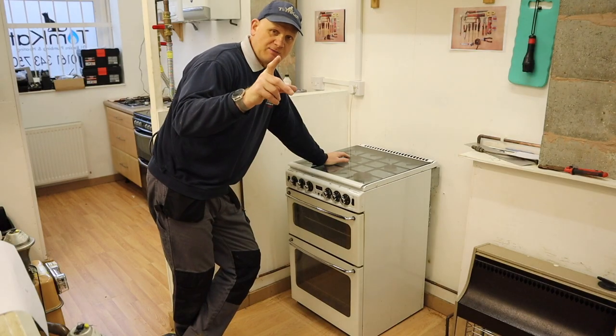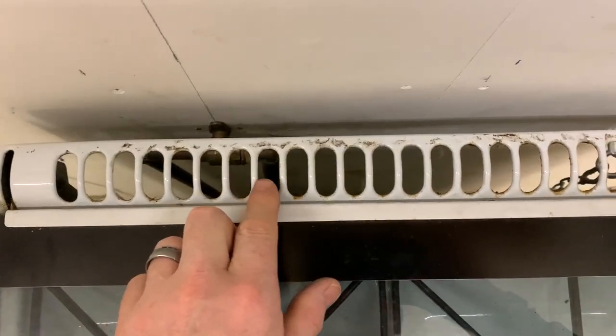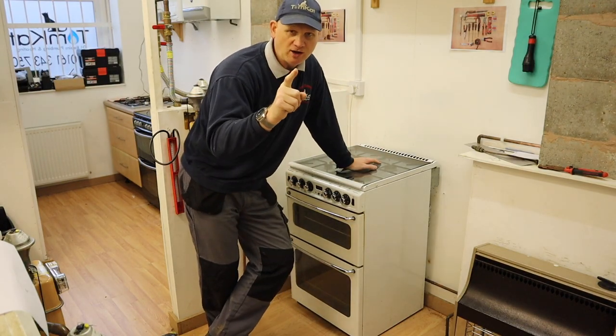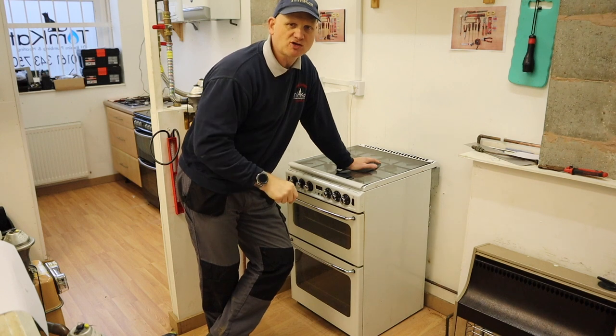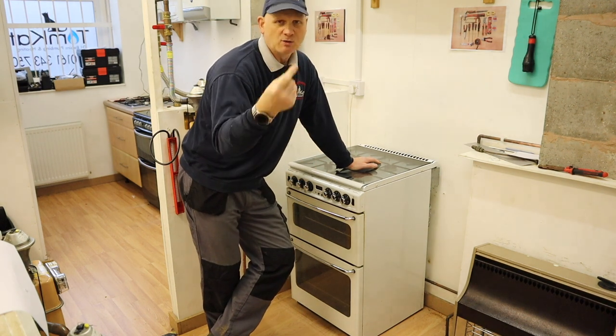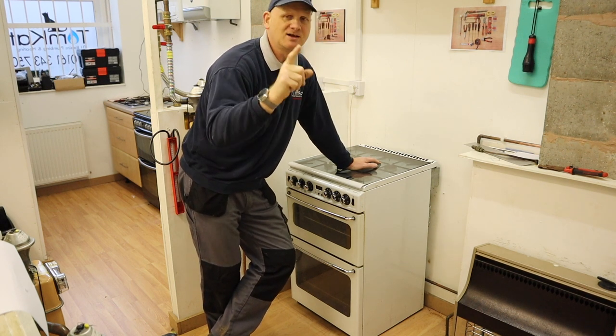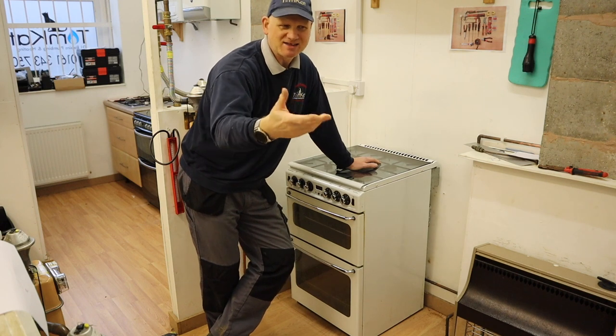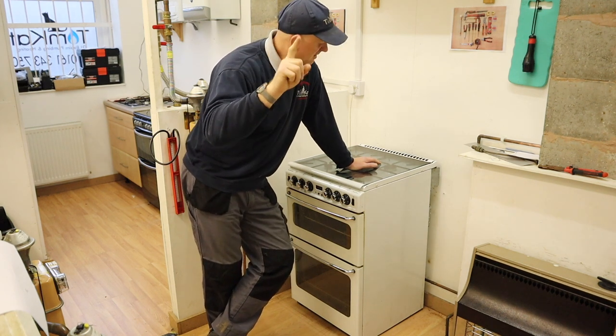Let me give you a quick tour around the cooker. The grill at the back is not just decorative — this is where the products of combustion come into the room. A cooker is a Class A flueless appliance, meaning its products of combustion come into the kitchen. We may need ventilation depending on room size, but you definitely require an openable window, or some other direct access to outside like a patio door.